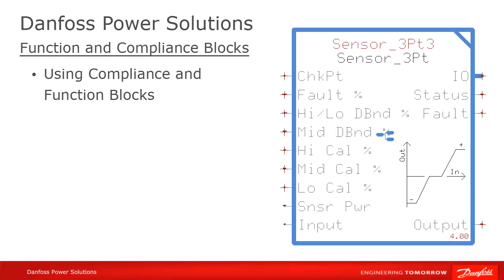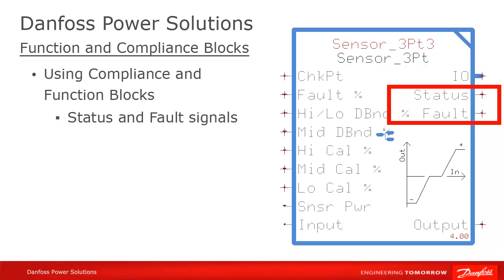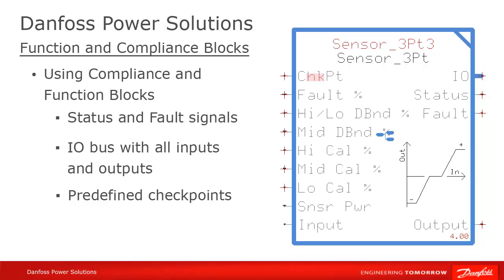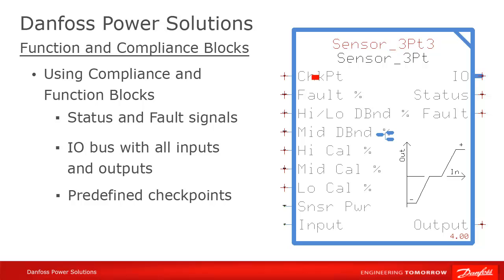For the function blocks, you'll see that we follow certain conventions. There's always a status and fault output, which follow a common pattern. There's an I/O bus, which contains all the input and output signals used and produced by the block. All the most recent blocks have checkpoints predefined for the block, which just need to be activated with the checkpoint signal. Keep in mind, however, that checkpoints consume memory in your program, so don't activate them if they're not being used.